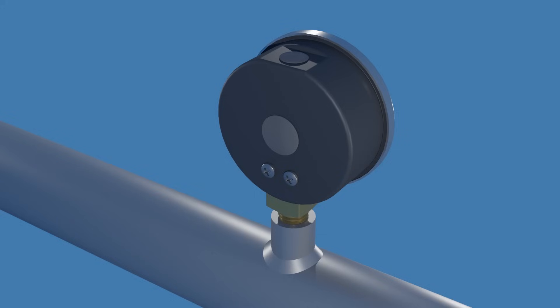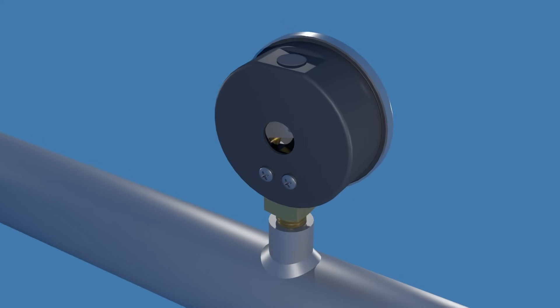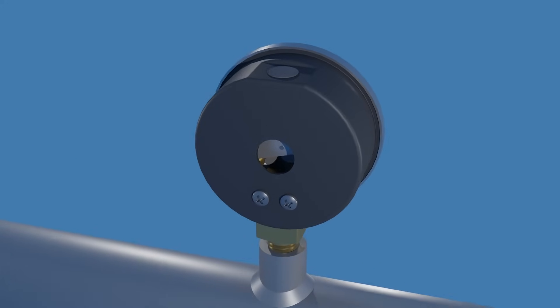Some pressure gauges have a blowout plug on the back. They act as a pressure relief mechanism designed to release the overpressure away from the operator in the event of a catastrophic failure of the pressure sensing element inside the gauge.